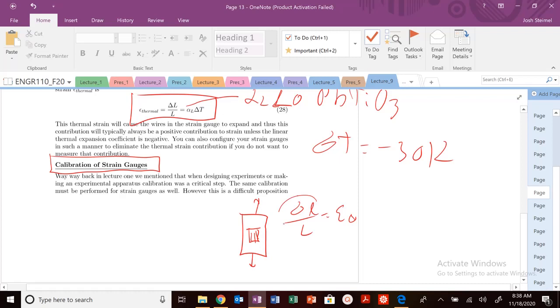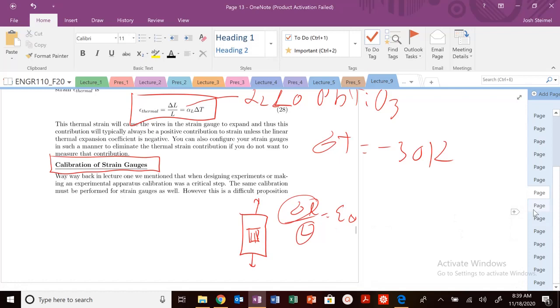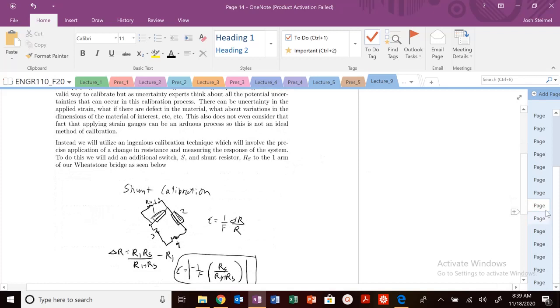What's the uncertainty in these values? And you get this propagation of error that, we might not know exactly, are these uncertainties overlapping or not, and people aren't really going to go through the work in order to do that uncertainty analysis. But what we actually do in order to calibrate strain gauges is this ingenious method, where we use this shunt calibration method.